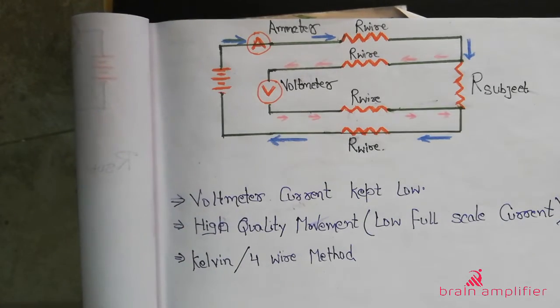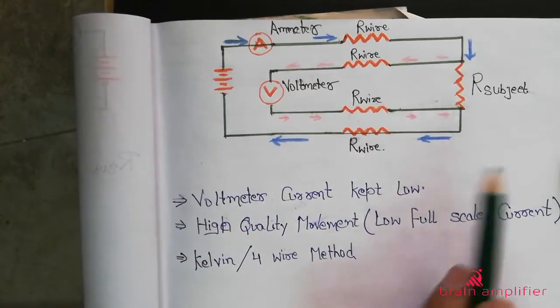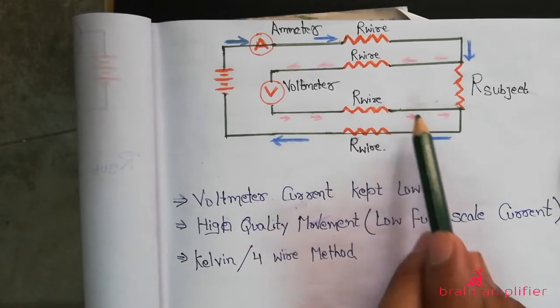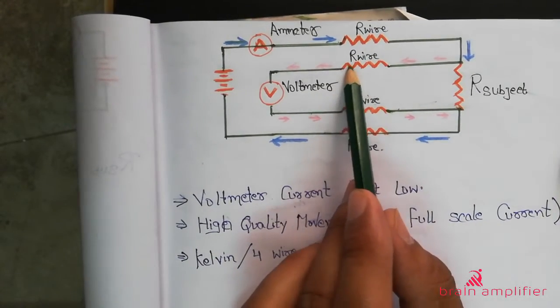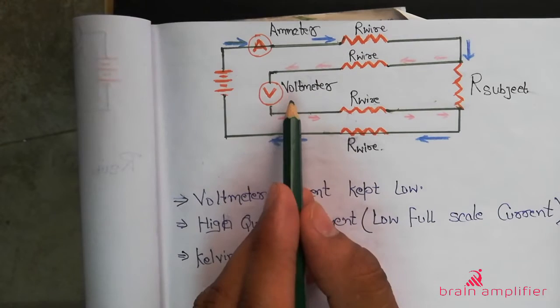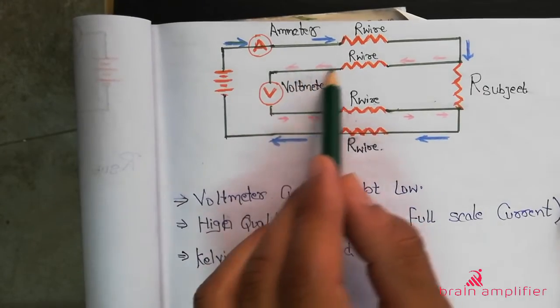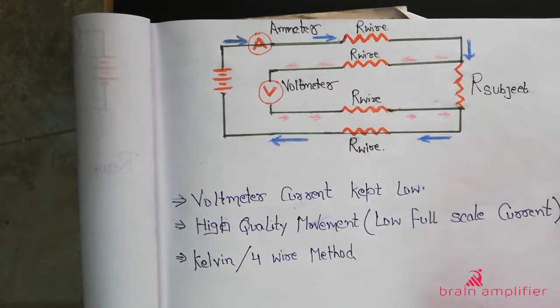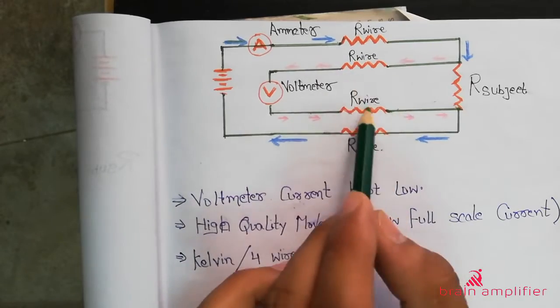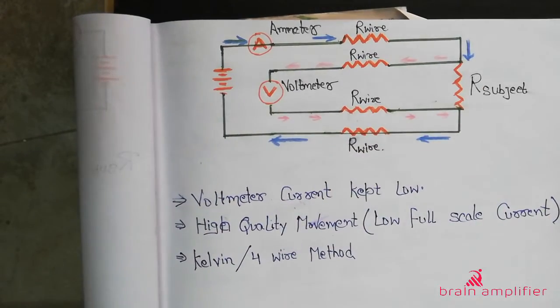You might say: if I have to measure from 50 meters, the voltage wires are also 50 meters long and should also introduce significant resistance. But that is not true, because the voltmeter measures with very high impedance. The current passing through the voltage circuit is insignificant — almost nil. If there is no current passing through that circuit, the R_wire of the voltage leads is no problem. So the voltmeter measures only R_subject.